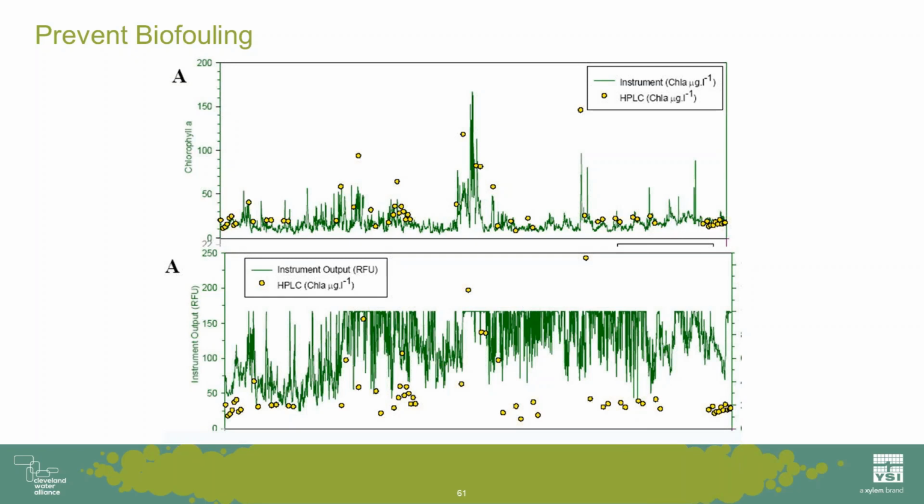On the bottom is a competing high accuracy chlorophyll sensor that shall remain unnamed, but which is still sold in the market today. This sensor has been pegged, and by that I mean that the sensor thinks there is an amount of chlorophyll that is maxing the sensor range out. That's because light is not penetrating the biofilm on the sensor's face. There's actually a mild growth of algae on the face of the sensor, and all the signal from that biofilm is directly being bounced right back to the photodetector. So this is a misleading outcome, and I see this all the time.